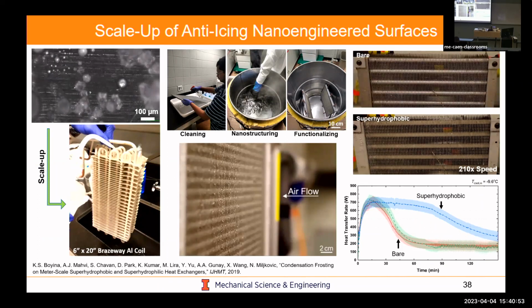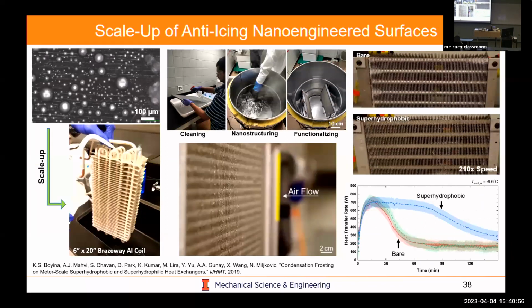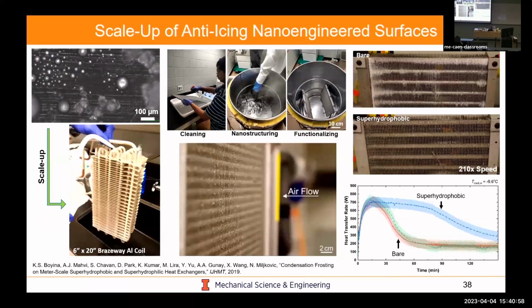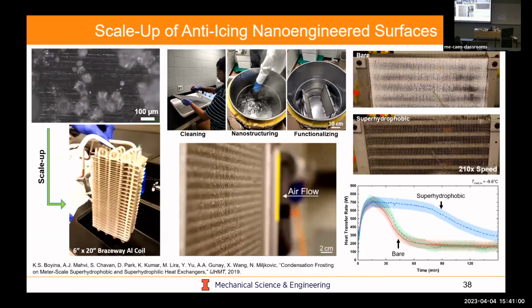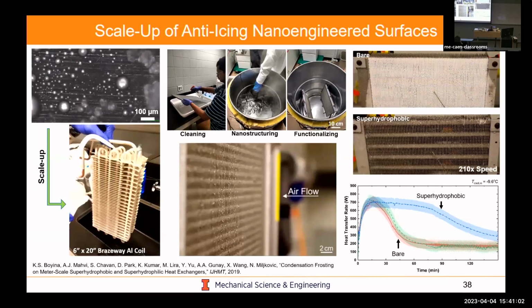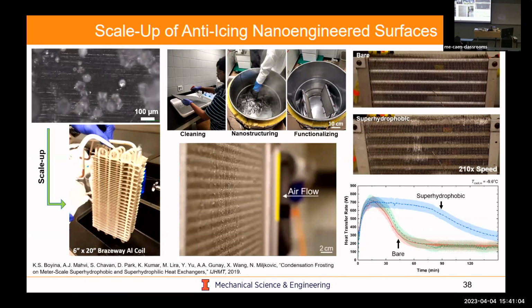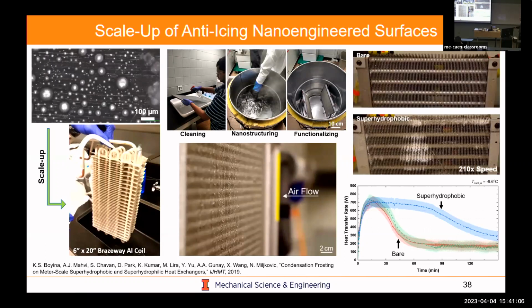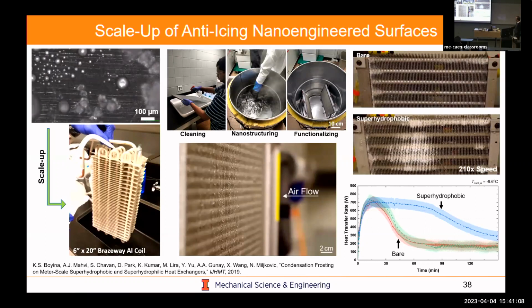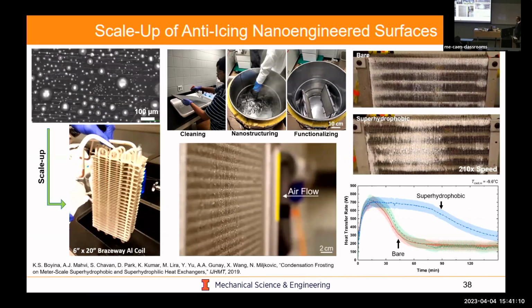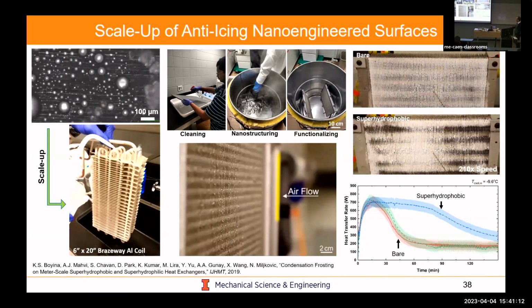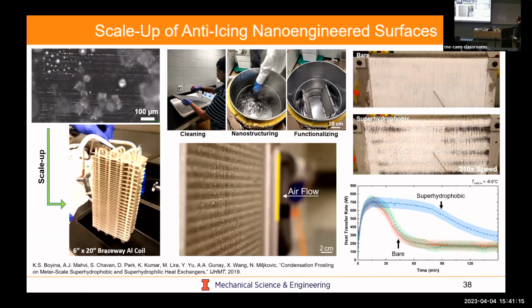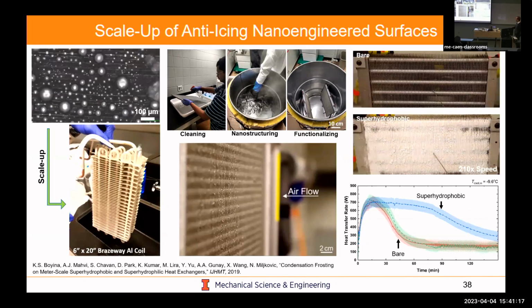You can see here, this is a bare heat exchanger, and this is a super hydrophobic heat exchanger. There's a very large delay in the icing time, about 2.5 times. So you could actually delay your de-icing cycle and save efficiency. If you plot the heat transfer rate as a function of time, your super hydrophobic heat exchanger maintains its performance over a much longer time compared to your super hydrophilic one or your bare one.